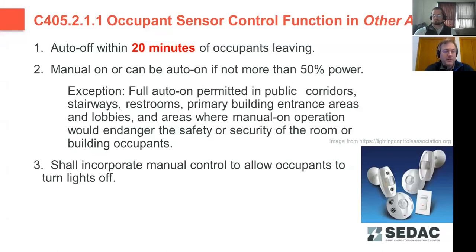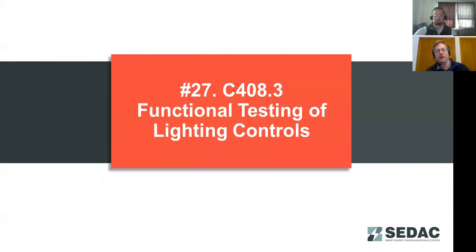Something important here is being able to have manual control so occupants can turn lights off. I had worked on a previous project in a library that they had added occupancy sensors, and these were going to be great energy saving devices, which they were. The challenge became in rooms where they were study rooms, and when people would go to try to use displays, there was too much light in the room, and they wanted to turn the lights off. There weren't any light switches for the occupants to turn it off to be able to see the monitors. So very, very important to have that ability for the occupants.